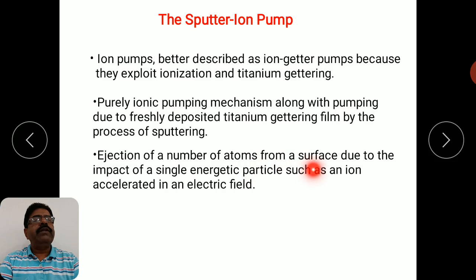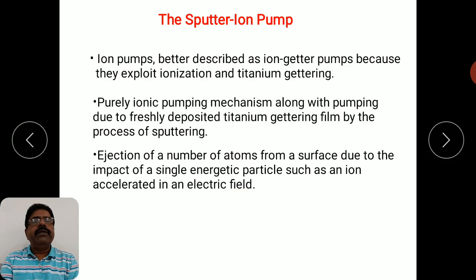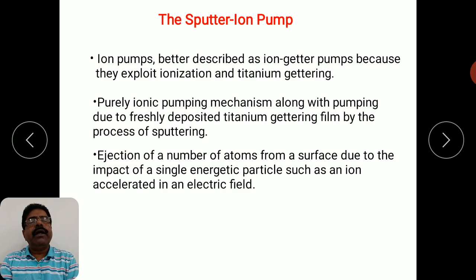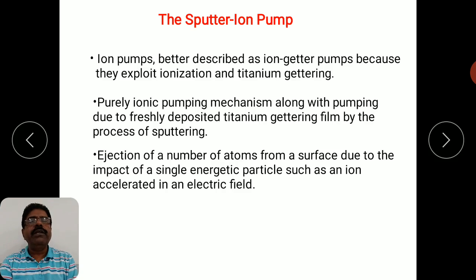Sputtering refers to the ejection of atoms from a surface due to the impact of an energetic particle such as an ion accelerated in an electric field. Gas molecules are ionized, and the positive ion is accelerated towards the electrode — the getter material, titanium. When the ion strikes the titanium electrode, atoms are sputtered and deposited elsewhere in the chamber, acting as a getter that traps or reacts with gas molecules.